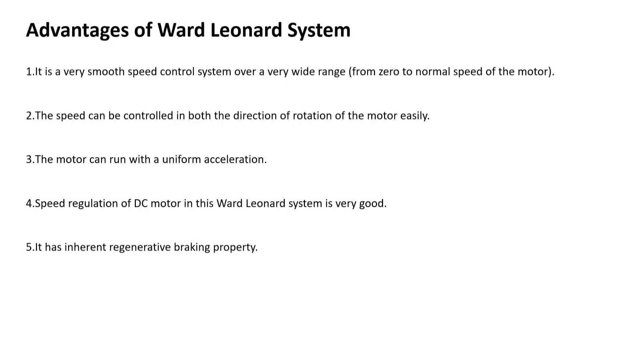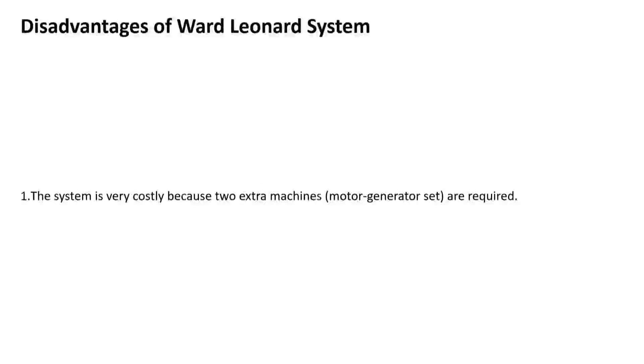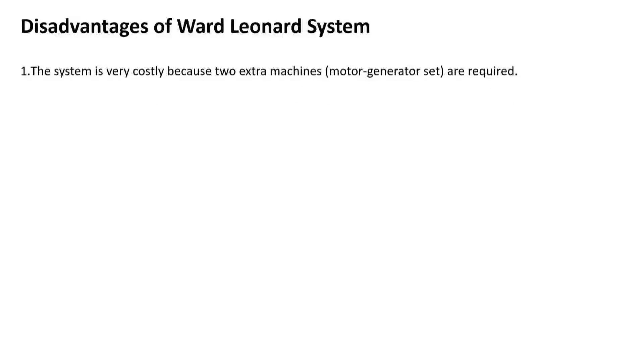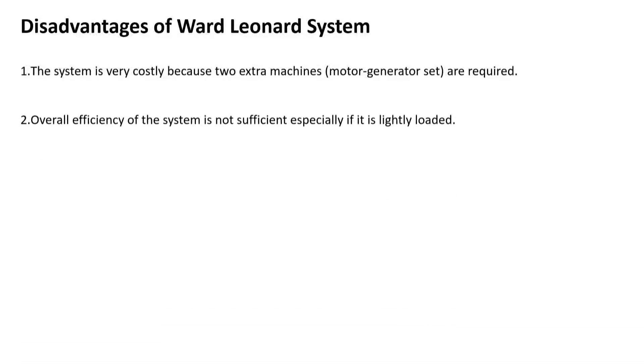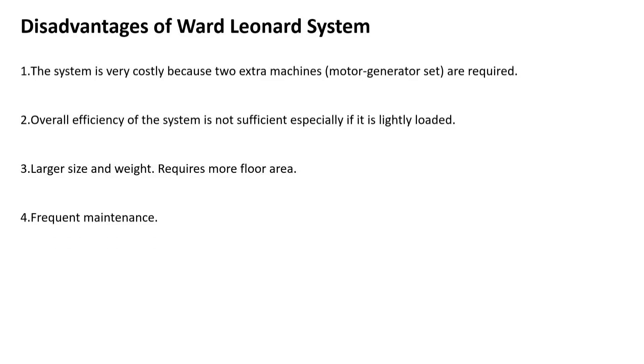The disadvantages of the Ward Leonard method are: the overall efficiency of the system is not sufficient, especially at light load; large floor space is required because of the large motors; it is costly because two extra motors — that is, a motor and generator — are required; frequent maintenance is needed; and it produces more noise.